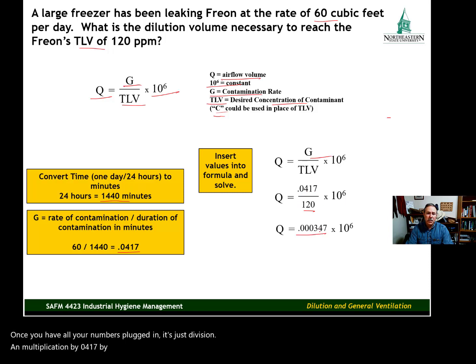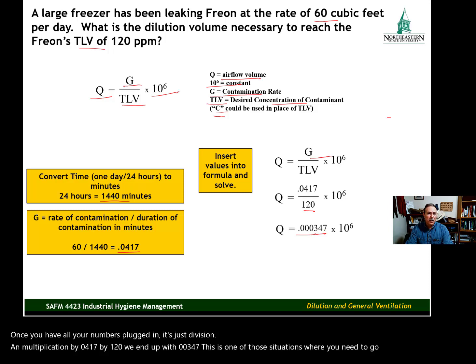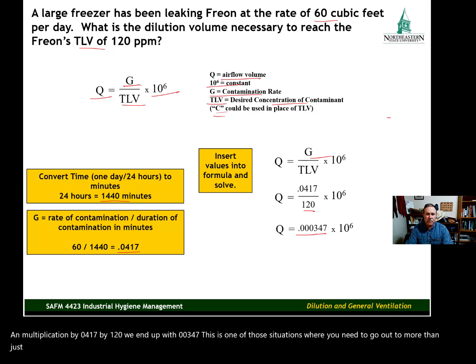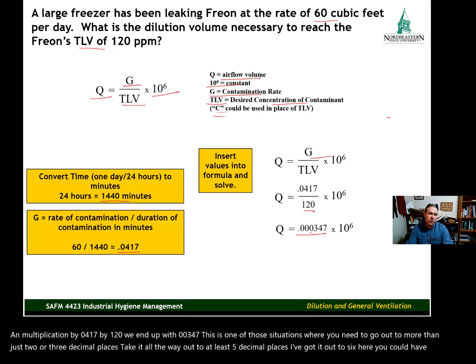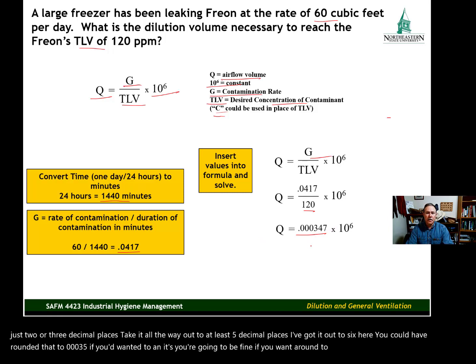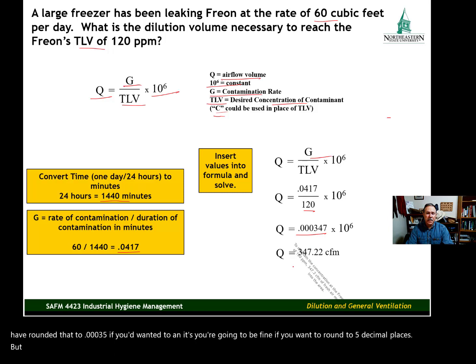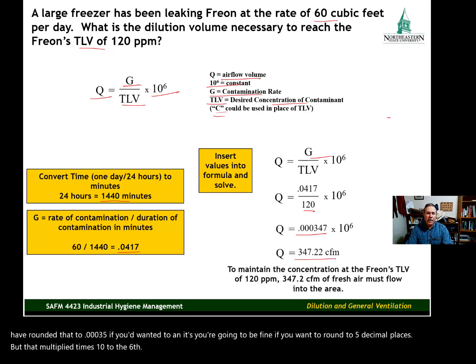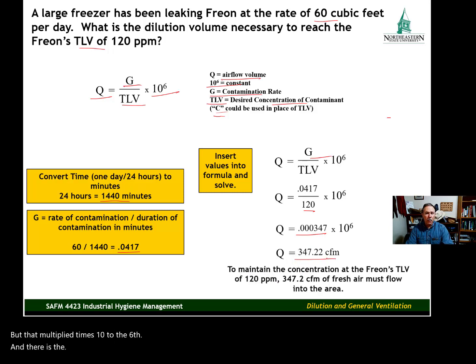We get 0.000347. This is one of those situations where you need to go out to more than just two or three decimal places — take it out to at least five decimal places; I've taken it to six here. You could round to 0.00035 at five decimal places and you'll be fine. Multiply that by 10 to the 6th power and there is your airflow volume in cubic feet per minute.